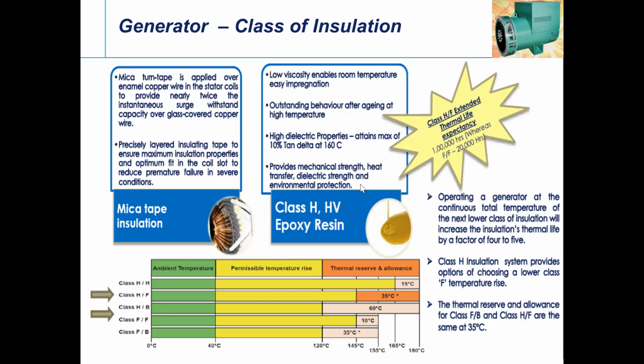There is insulation with a temperature rise, where the ambient temperature has been considered as 40 degrees in India, around that. Of course, it is very unique. Rajasthan has got more than 48, or Delhi, so it is invariably different. So considering ambient temperature as a standard, there are class F and other classes of insulation, but predominantly, based on the temperature rise considered for the customer demand or requirement, the present generators are manufactured with class H insulation, which has been one of the predominant for high voltage machines, where the epoxy also plays an important role. So for example, when we do a high voltage test or a surge test, such things require insulation, which is very important.